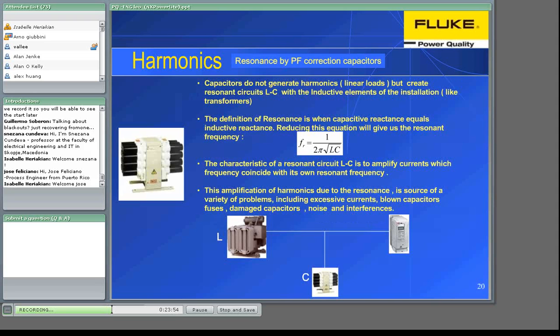Resonance effect. Capacitors do not generate harmonics. They are linear loads, but create LC resonance circuits with the inductive elements of the installation. The definition of maximum resonance is when capacitive reactance equals inductive reactance. An LC circuit consists of an inductor, represented by the letter L, and a capacitor, represented by the letter C. When connected together, an electrical current can alternate between them at an angular frequency.